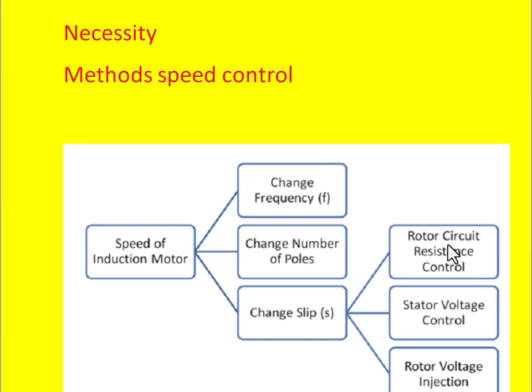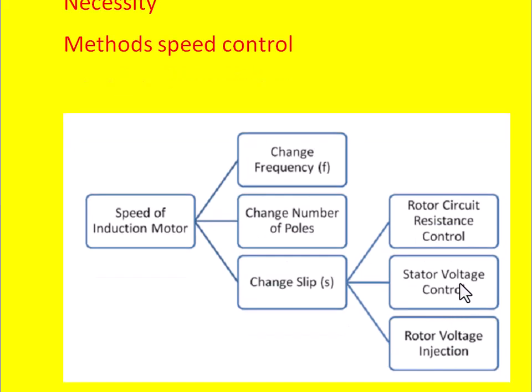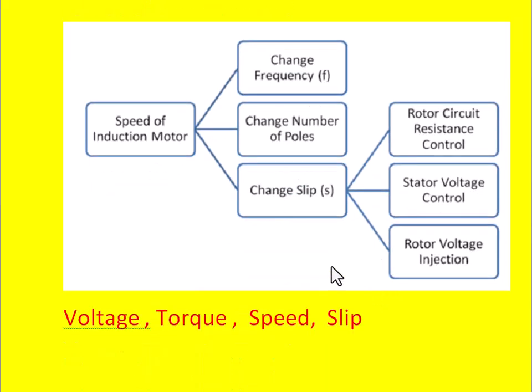To get the change in slip, there are three methods available: one is in the slip ring induction motor — the rotor circuit resistance control method. Next is the stator voltage control method, which is used for the squirrel cage induction motor. Similarly, the rotor voltage injection method is used in the slip ring induction motor.